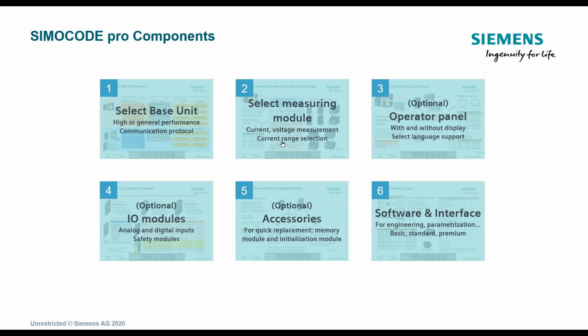And then what type of measuring module? Are we just going to measure current only? Or are we going to measure current and voltage together? Those are the 2 main things we have to worry about. Everything else that I speak of is optional. Operator panel is optional. You don't need it. The I/O modules, analog, digital, safety module, earth fault modules, and so forth are optional.